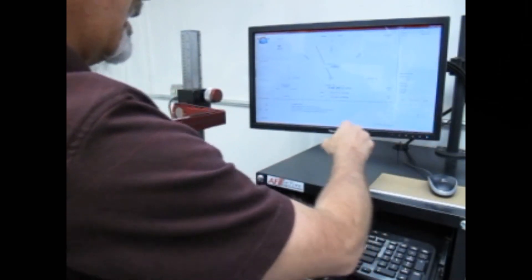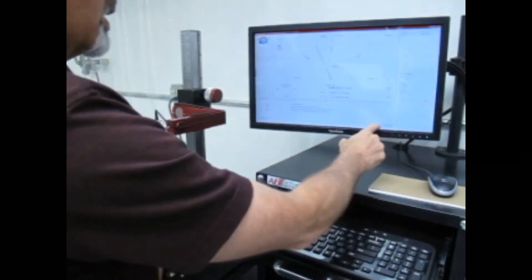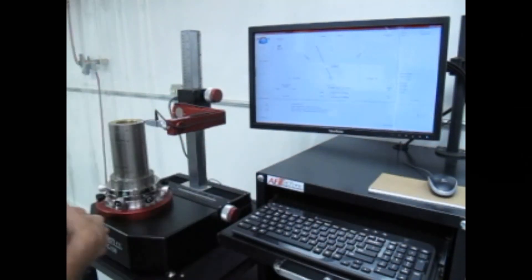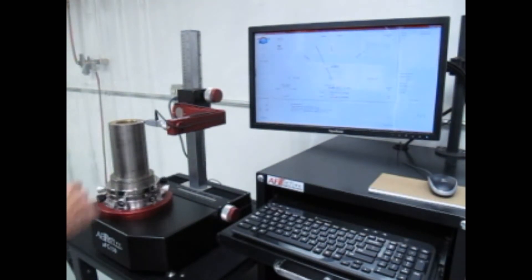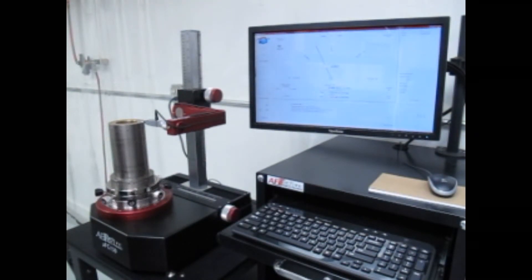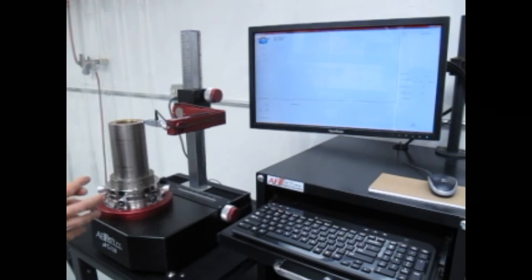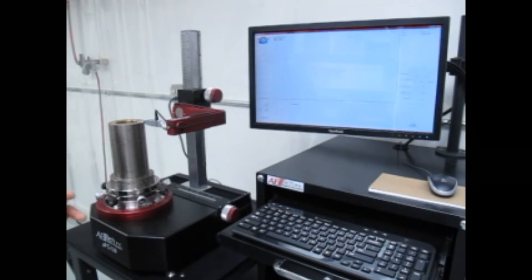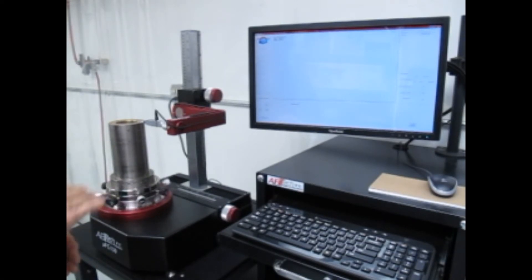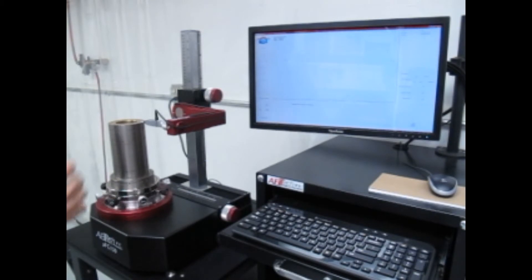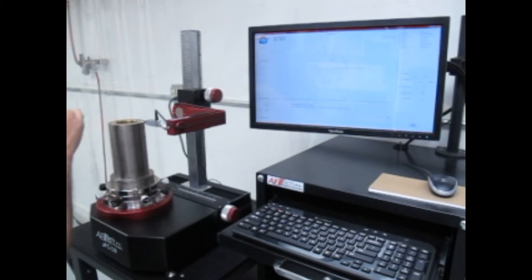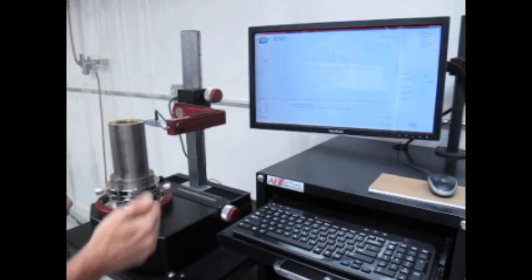And I'm going to select top or bottom and it is at top there. I'm going to apply that and then I have the option of using the motor or manual spin. So just like in concentricity, it's going to take a trace one revolution of this top surface and it's going to give me the TIR. It's going to give me the flatness of that surface.